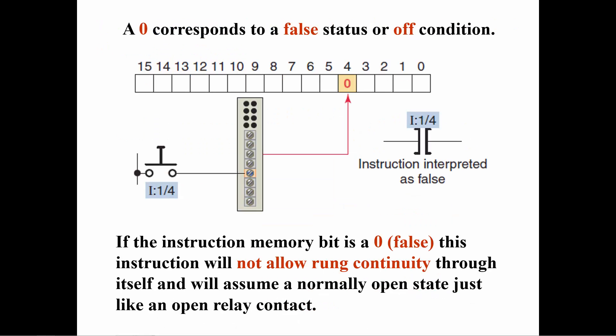If the external switch is not closed, a 0 is placed at the specified address in the input table and the examine if closed instruction becomes false, and there is no rung continuity through the contact. This is the same as a normally open contact on a relay whose coil is not energized.